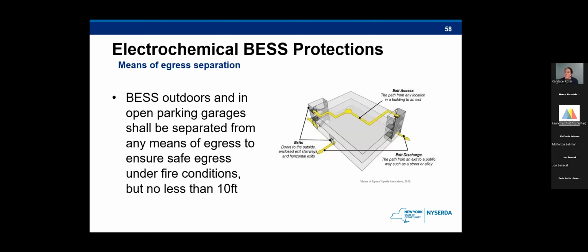And next we have the means of egress separation. So basically this one really focuses on ones for storage systems that are in a parking garage or outdoors. So egress from an open parking garage is very important, and these systems should not be within 10 feet of those pathways.